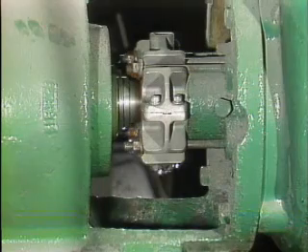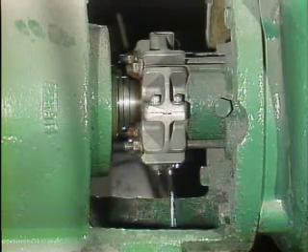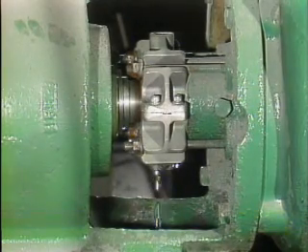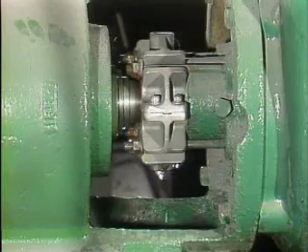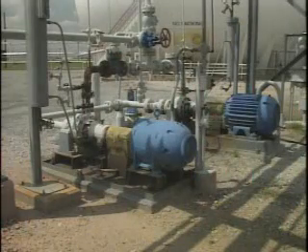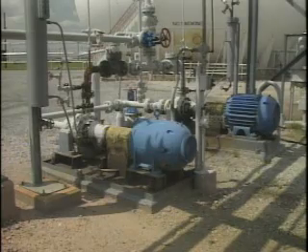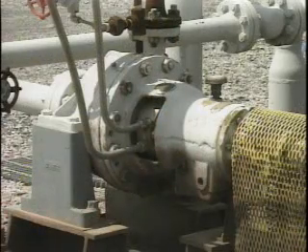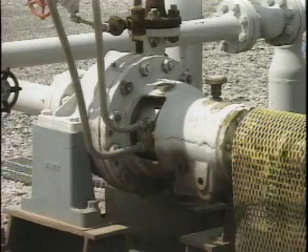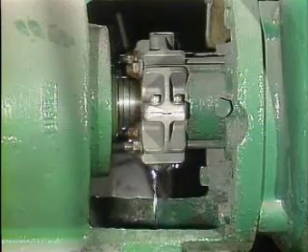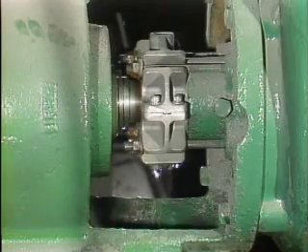Although mechanical seals are designed to last a long time, some of them fail well before their life expectancy is reached. One of the most common causes of seal failure involves problems with the equipment that the seal is installed on. For example, misaligned shafts, bent shafts, or bad bearings could easily cause a mechanical seal to fail. Sometimes, however, mechanical seals fail for other reasons.